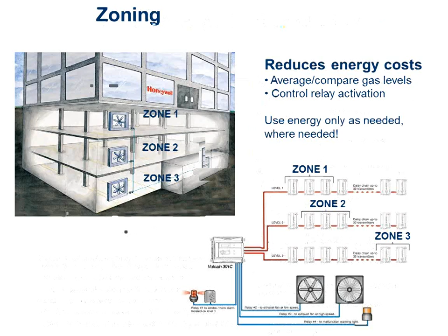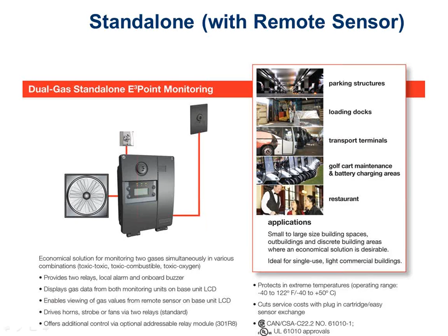I can also have network systems using BACnet or other types of communication, and there's even wireless systems as well now. Some of the manufacturers have wireless systems, which is useful from an installation cost standpoint. The only negative really is I've got to go around and change batteries because there's no continuous power available, but that's not the end of the world. And sometimes you can hardwire them to a power source. So maybe I can get a power source, but I can't get a communication source. That does come up sometimes as well.